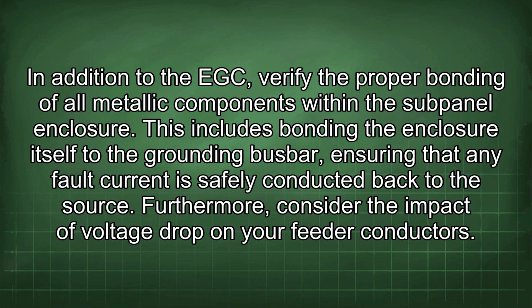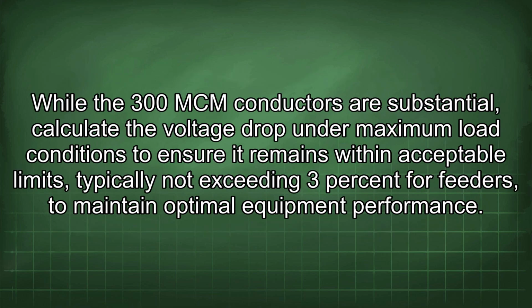EGC, verify the proper bonding of all metallic components within the subpanel enclosure. This includes bonding the enclosure itself to the grounding busbar, ensuring that any fault current is safely conducted back to the source. Furthermore, consider the impact of voltage drop on your feeder conductors. While the 300 MCM conductors are substantial, calculate the voltage drop under maximum load conditions to ensure it remains within acceptable limits, typically not exceeding 3% for feeders, to maintain optimal equipment performance.